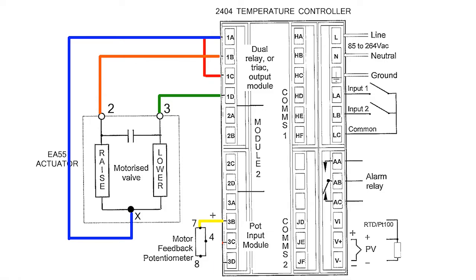Next, wire terminal 3C of the temperature controller to terminal 4 of the motorized valve actuator. Next, wire terminal 3D of the temperature controller to terminal 8 of the motorized valve actuator.